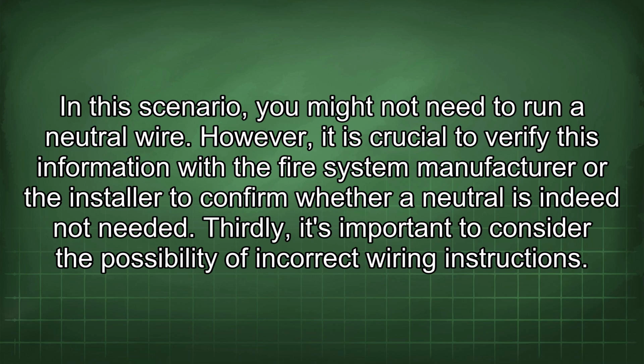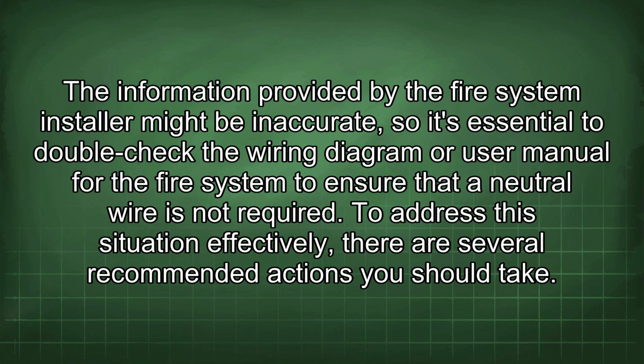Thirdly, it's important to consider the possibility of incorrect wiring instructions. The information provided by the fire system installer might be inaccurate, so it's essential to double-check the wiring diagram or user manual for the fire system to ensure that a neutral wire is not required.